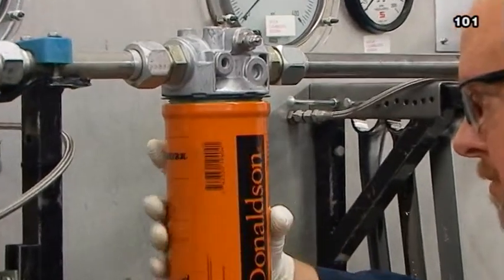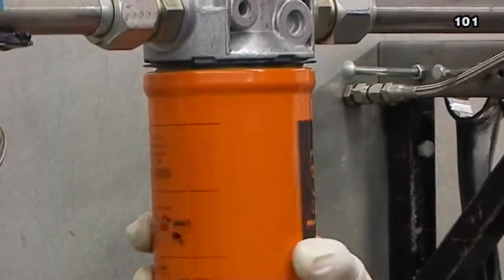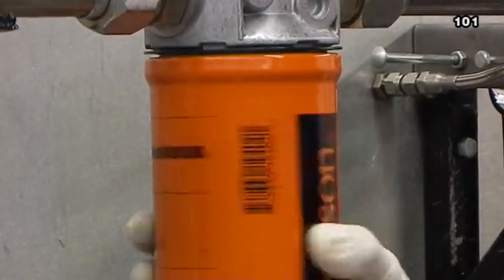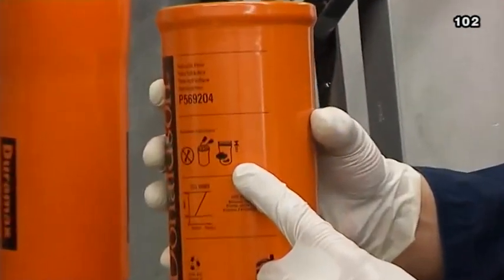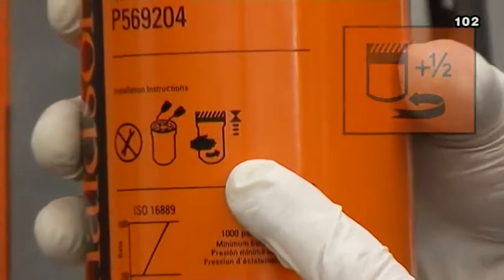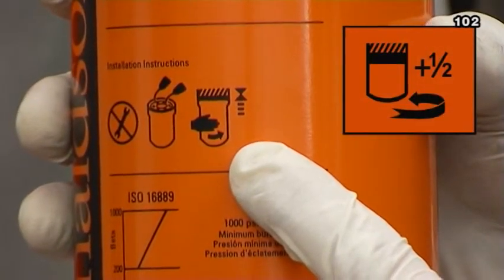As the sixth step, install the spin-on filter, spinning it on until the top of the gasket first contacts the sealing surface. Then for final tightening, follow the guidance of the icons which appear on the filter housing. Do not over-tighten.